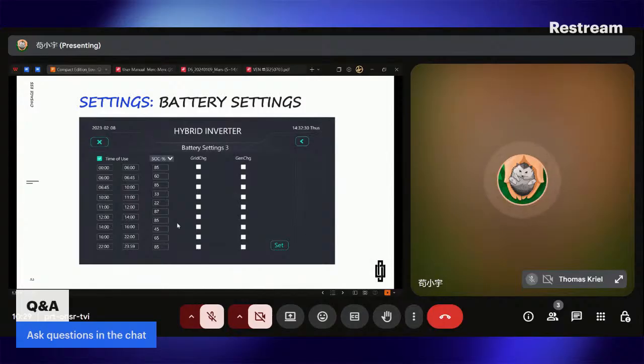Then it's battery settings 3, and we can see the time of use function here. So if you want the battery to only charge or discharge at a certain time, you can check it here. We can see 2 options, grid charge and generator charge. If you check the checkbox, that means it will use grid or generator to charge it. If you uncheck it, that means it will only discharge to this SOC. And if you click on the SOC percentage button, you will be able to select the voltage, so that you have 2 ways to set this.